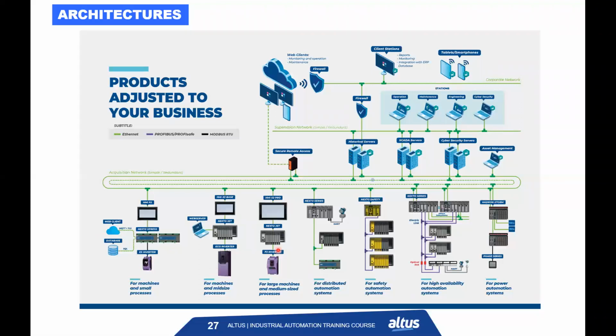Here again, for large machines and medium-sized process, is another way to use it, with distributed I/O, so we can use modular systems next to each other to connect to modular remote I/O and to another compact. Here we have a sample for safety automation with SIL3. And our next series, with redundancy for high availability. You can see two main processors running in redundancy, and the network with two buses in redundancy, with two heads in the I/O and with hard connection.